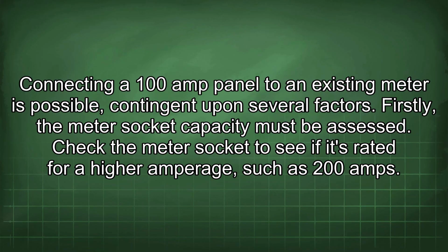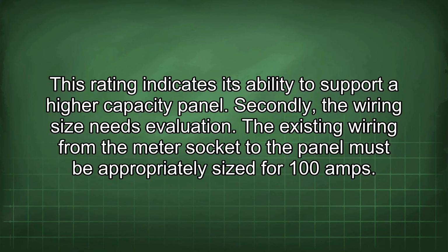Connecting a 100 amp panel to an existing meter is possible, contingent upon several factors. Firstly, the meter socket capacity must be assessed. Check the meter socket to see if it's rated for a higher amperage, such as 200 amps. This rating indicates its ability to support a high capacity panel.